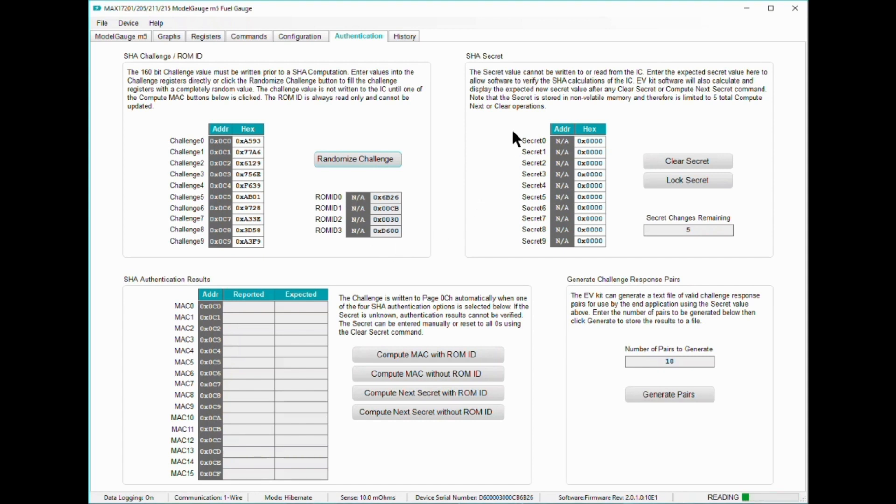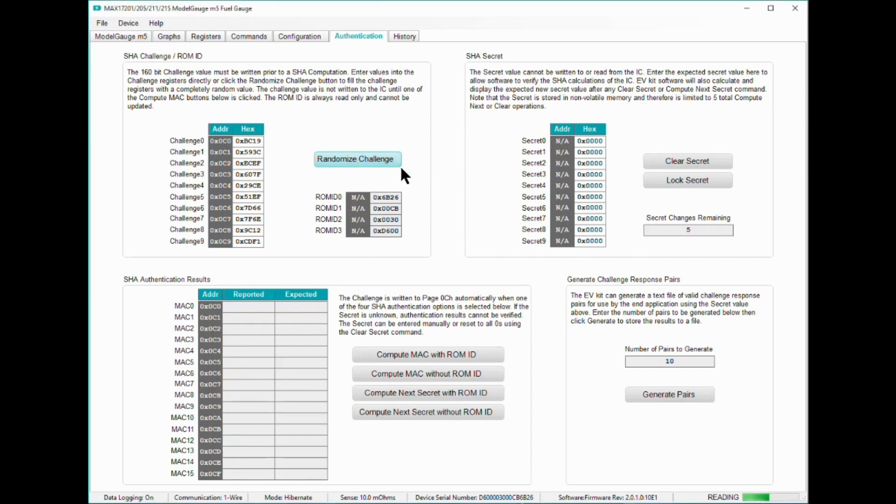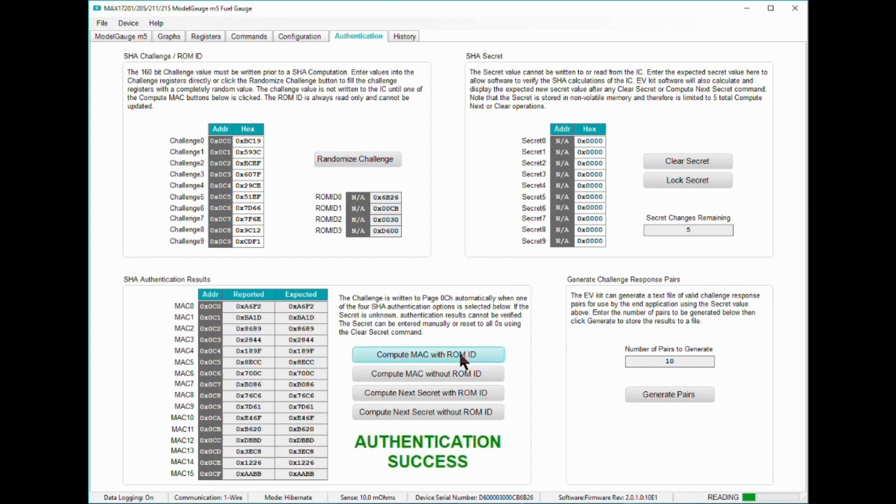This unique 64-bit ID pertains to the specific 17211 I have here on my desk. The upper right-hand corner shows the 160-bit secret key the EVAL software has in memory. In a freshly minted 17211, the secret key is all zeros by default. Remember, the secret key on the MAX17211 cannot be directly written or read by the user.